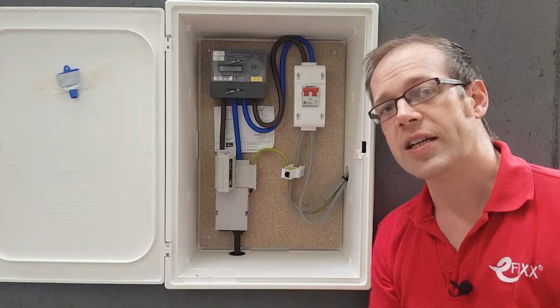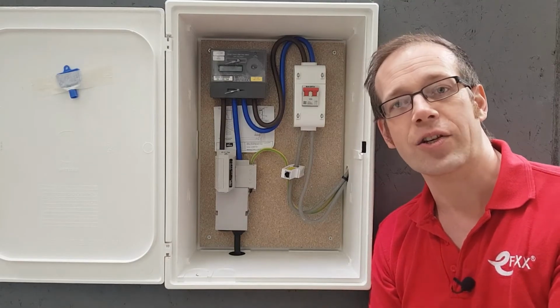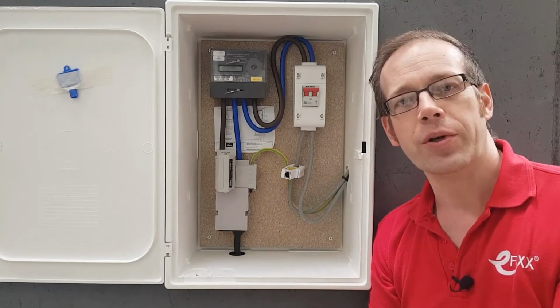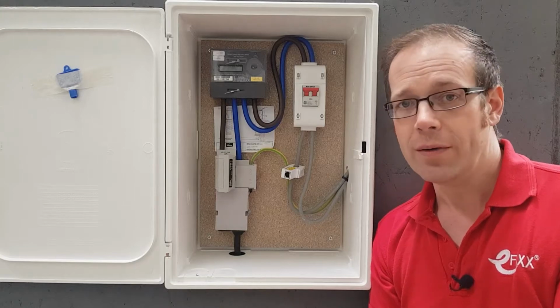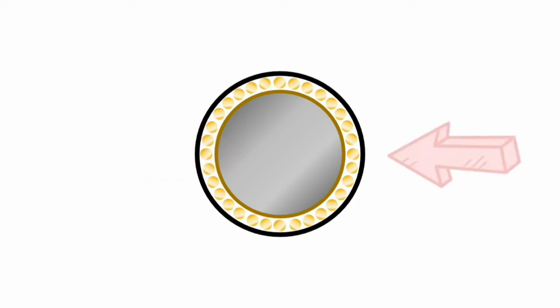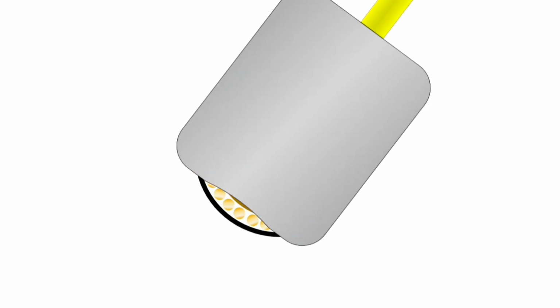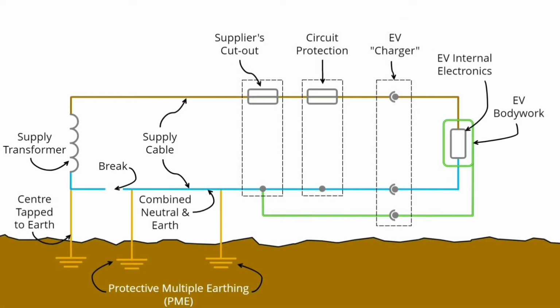To try and minimise the chances of losing the combined neutral and earth connection outside the property, there's a couple of precautions that the DNO take. One is to use a concentric cable where the line conductor is in the middle of the cable and the combined neutral and earth is wrapped around the outside. This means if anyone accidentally cuts through the cable with, say, a shovel, the line conductor is likely to be disconnected before the neutral and earth, meaning that the metalwork in the property won't go live.